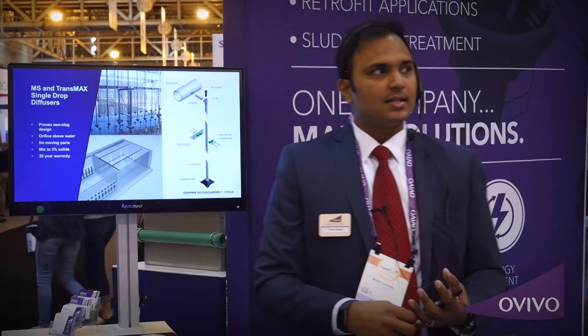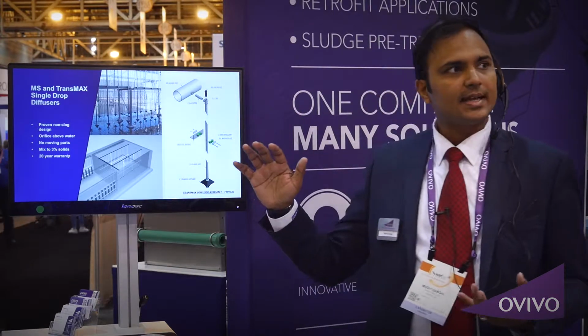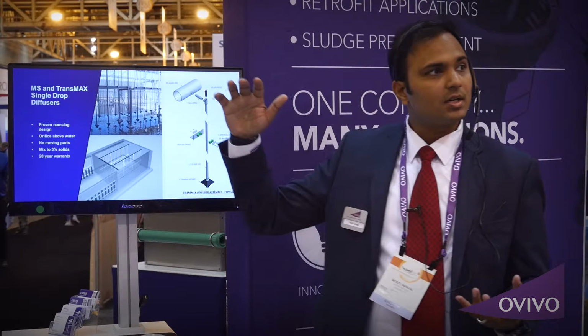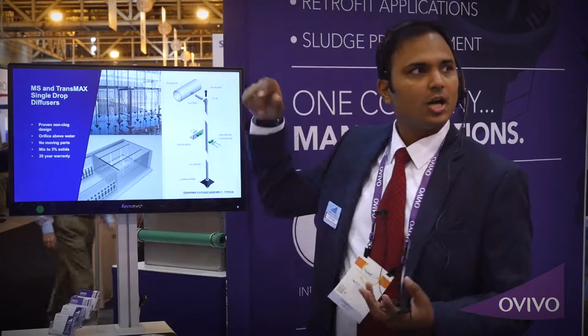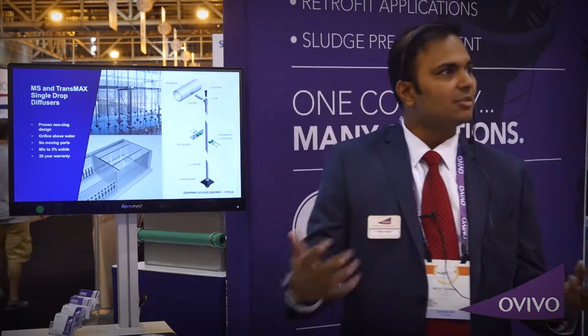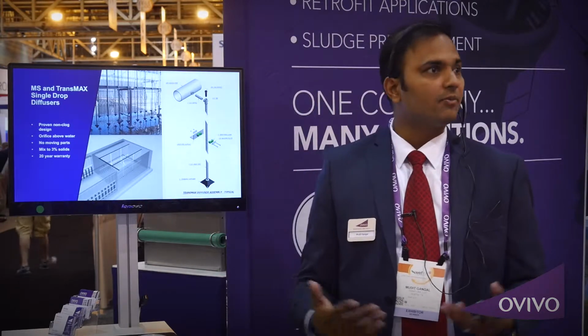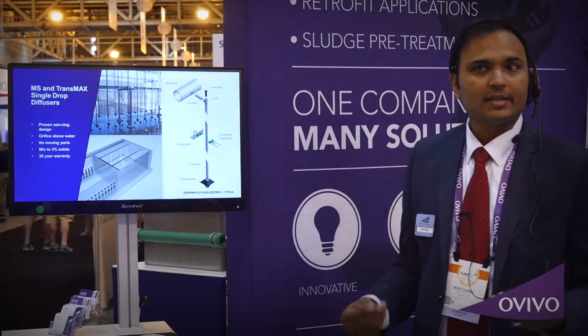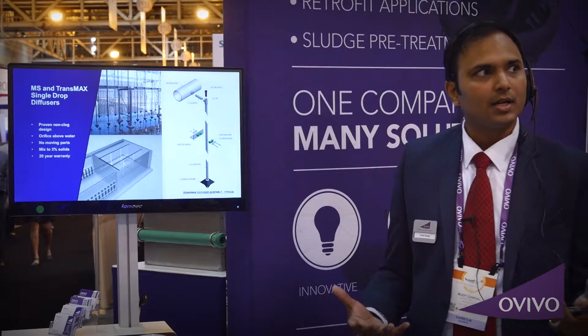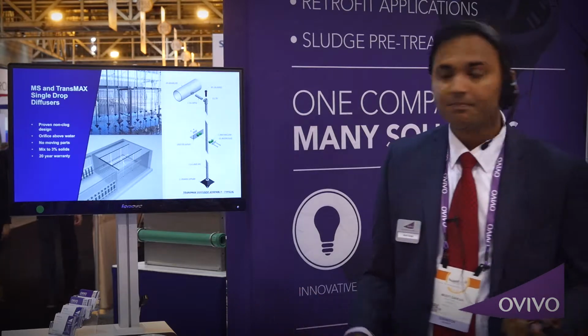One of the key things that we were discussing, the challenges with aerobic digestion, is being able to mix these thick sludge tanks. And that's where the Transmax diffuser comes in, where essentially it's a non-clog design. You have an orifice above the water, so nothing inside the sludge that you have to maintain. All you have is a little orifice on top, which you can unplug and just hose down. So it's easy to clean. It's a very robust process that's been running for over 20 years at several plants. And so it's a very operator-friendly way of mixing and aerating the sludge and getting your aerobic digestion. You can mix up to 3% solids, and there are no moving parts.